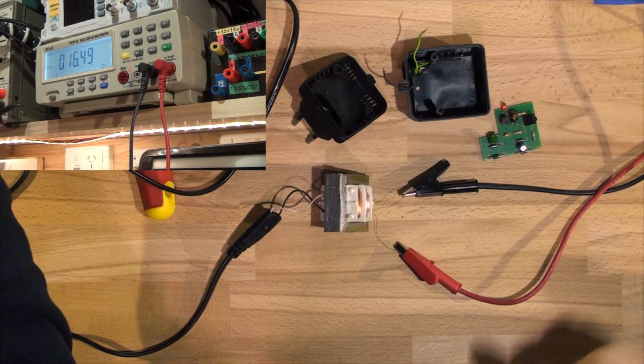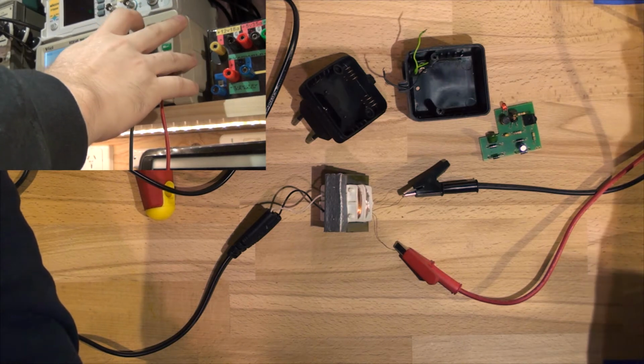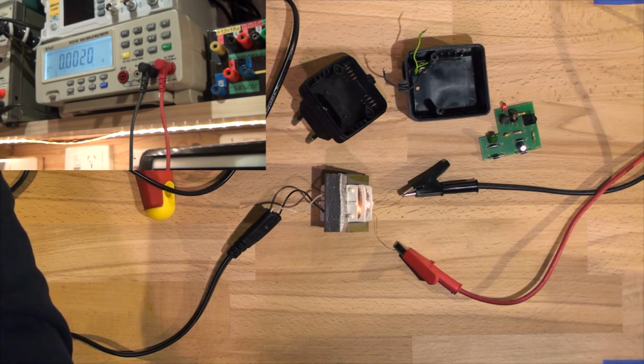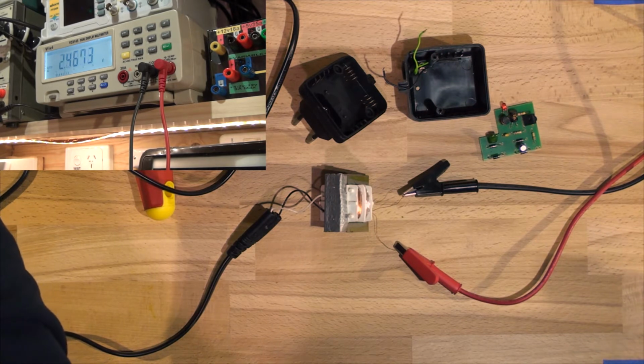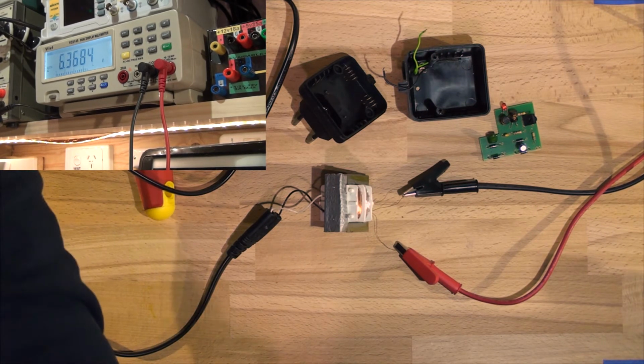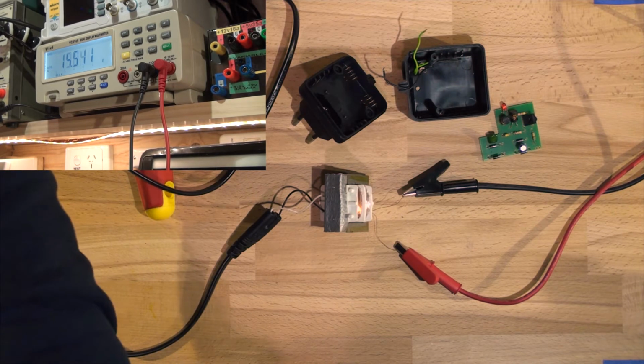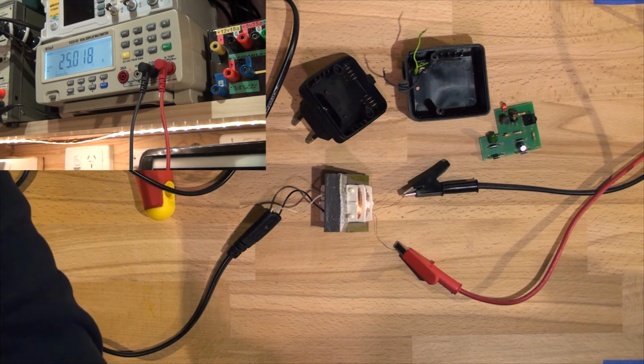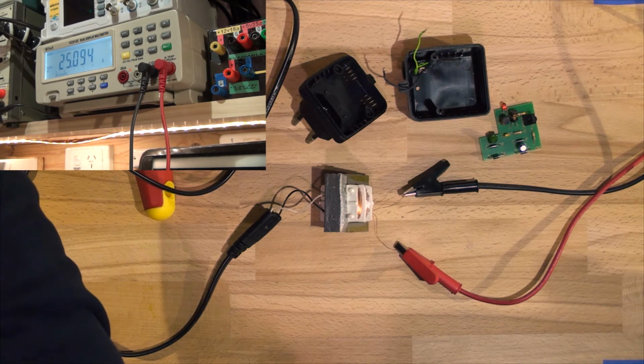Alright, so here it is. Let's go to voltage, AC, and slowly increase the variac. And it looks like the transformer's working just fine. So that's 120 volts, and 240 volts, the transformer's output is 25 volts. So it's about 1 to 10. The transformer is working fine, that's good.